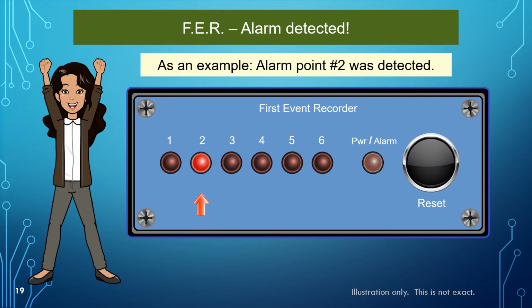Here's an example of point number 2 activated. So the FER will stop scanning and point number 2 will illuminate bright. Then the power alarm LED will start to flash. It will stay in this state with number 2 lit bright and the power alarm LED flashing. It will remain this way until you push the reset button. So even a momentary pulse will still latch on to that state.